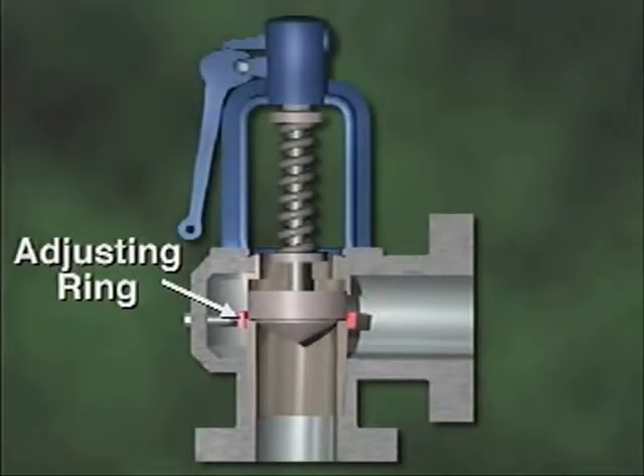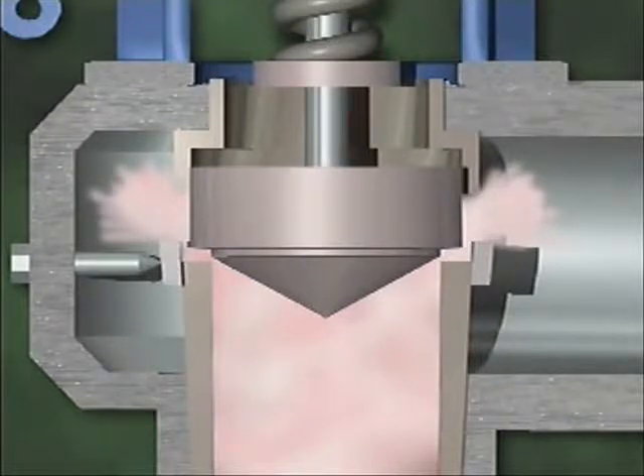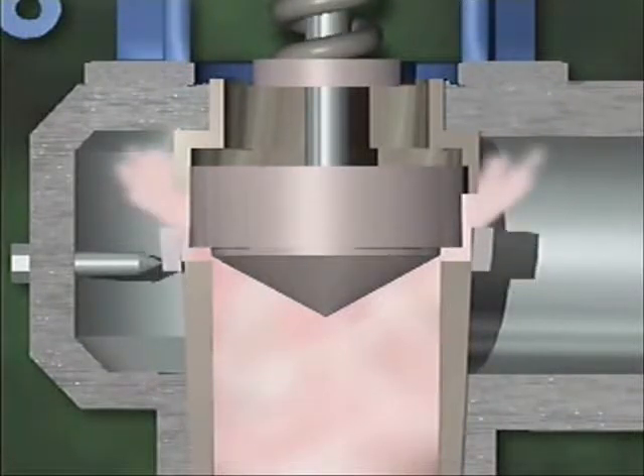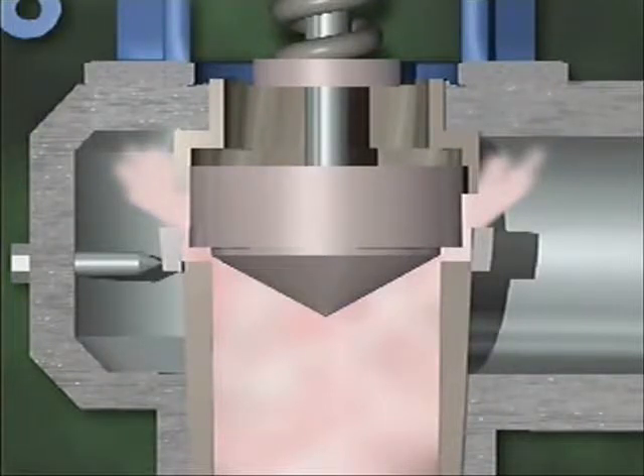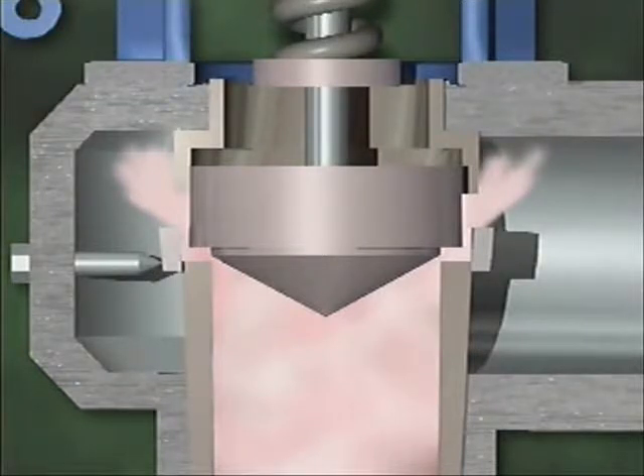Blowdown can be adjusted by changing the setting of the valve's adjusting ring. The position of the disc in a safety valve is determined by the amount of system pressure and the angle and velocity of the steam striking the disc. When the adjusting ring is in the raised position, the escaping steam is directed right at the disc. The velocity of the escaping steam exerts a great deal of upward force because most of the steam strikes the disc closer to a 90-degree angle. The system pressure must therefore drop well below the popping pressure before the spring can force the disc back onto its seat, so raising the adjusting ring increases the blowdown of the valve.